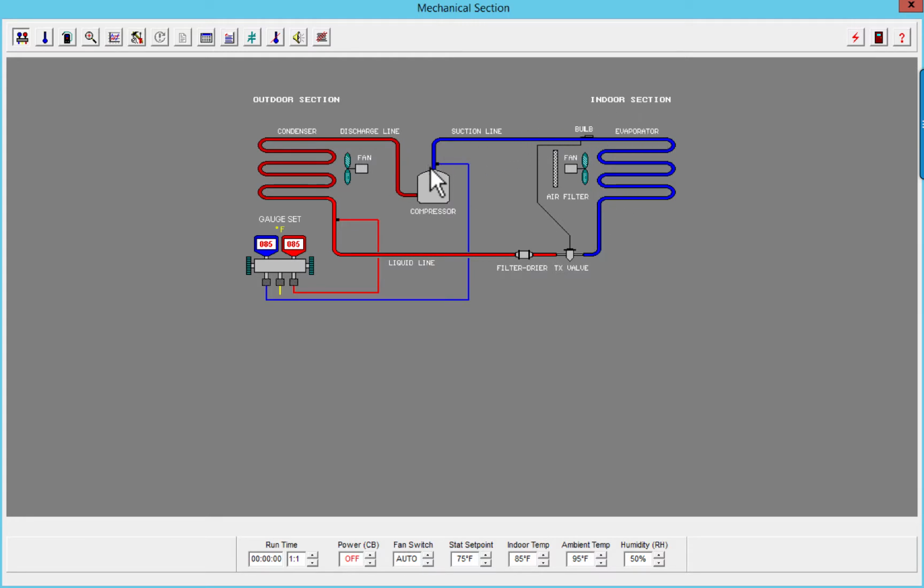It is going to show me the pressure of the refrigerant throughout the low side of the system, but what it's really telling me is the temperature at which the liquid refrigerant is boiling off and becoming a vapor. It's my evaporation point. Okay, and there's different names for it, but it's the point at which my refrigerant is boiling off and becoming vapor. It's the temperature that the latent heat change is happening.